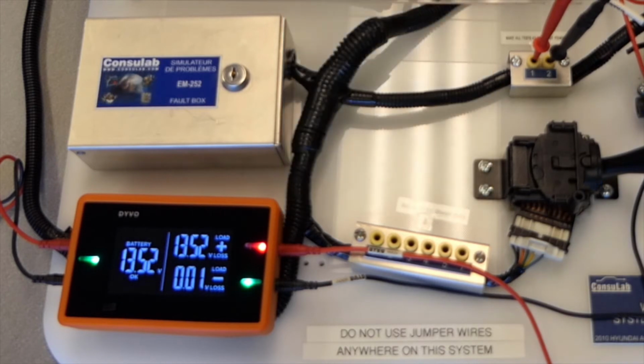Now immediately I see that for my ground I get a green LED and I see 0 volts on my ground side. So I know that my ground is good. What we don't have is our voltage side because we have a red LED. So that positive LED is red. That tells me there's an issue, and we can see we have 13.52 volts that are being lost in the positive side of the circuit.